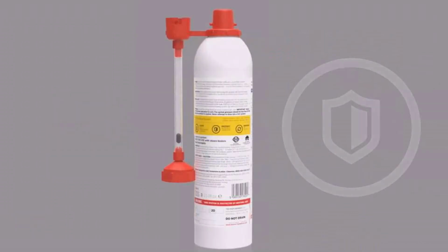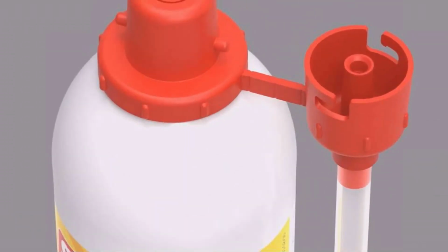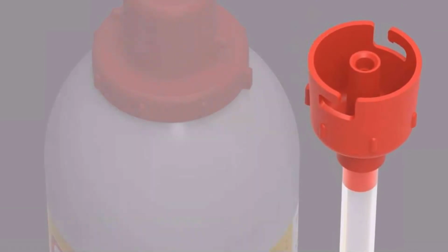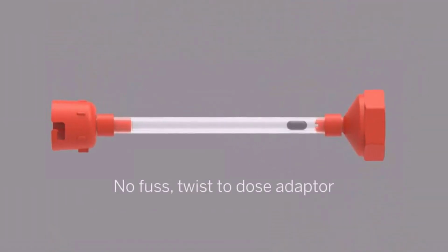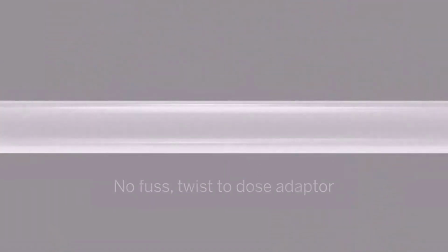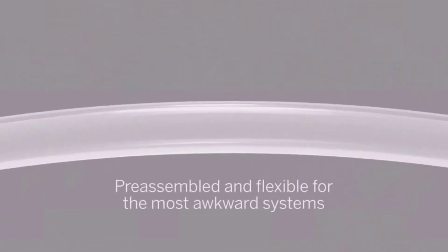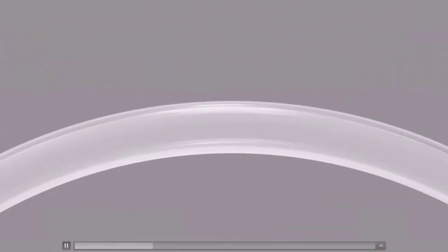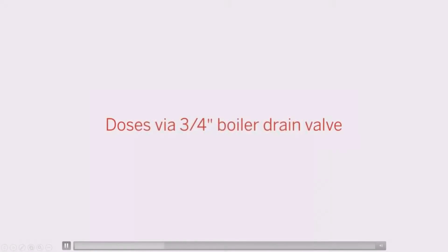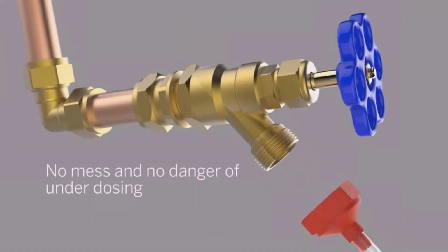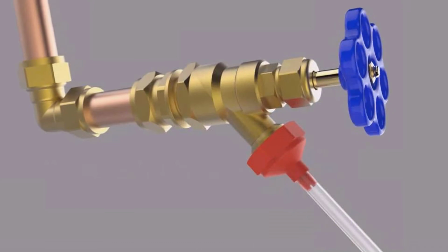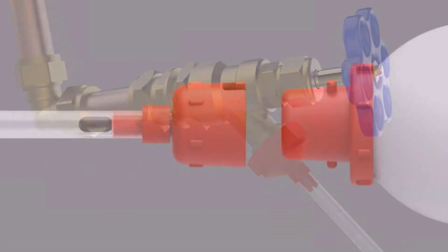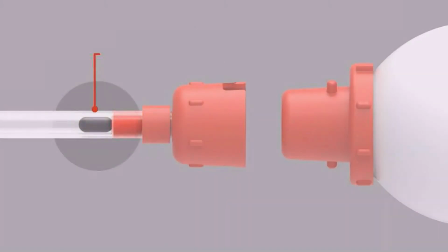One of the key things here, it says a suitable inhibitor must be added to the system. All systems have to be flushed and drained using an appropriate proprietary flushing agent. So first, they recognize that there's corrosion inside all hydronic systems, and that'll create corrosion sludge. It causes damage to the pump, valves, boiler noise, circulating problems. When new, system fluxes can be evident in the system, which can lead to damage to system components.